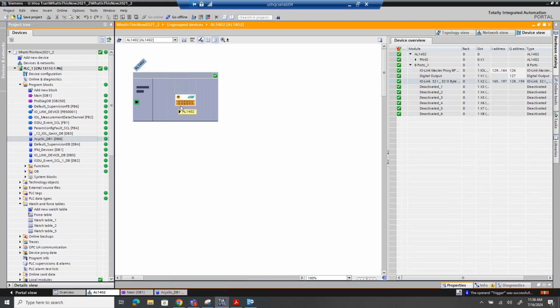There are other videos that show you how to set it up. In my case, so that we don't get any error messages because I only have one IO-Link sensor connected, in the device configuration, here's my master all set up. Ports I'm not using have to be deactivated so that they don't cause a fault. And here I just have port number 1 set up for IO-Link 32 in, 32 out, to make sure I can plug into any IO-Link sensor and work with it.